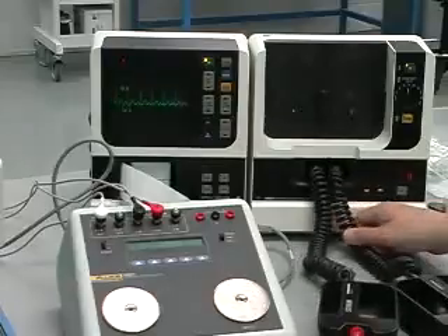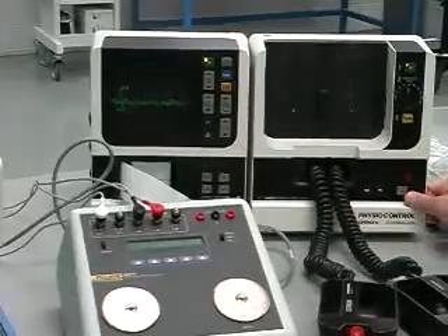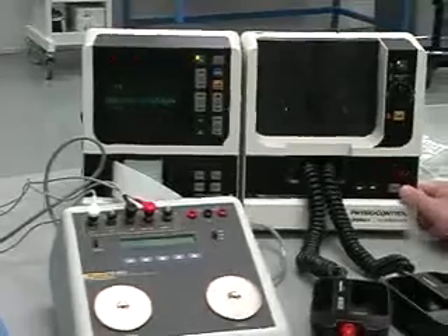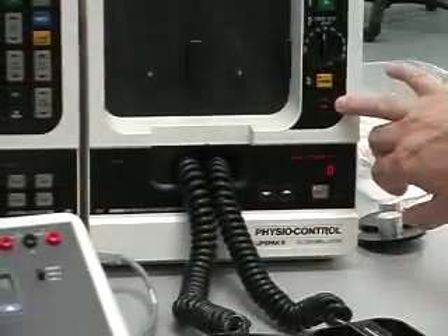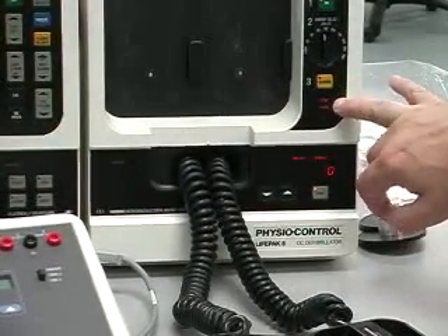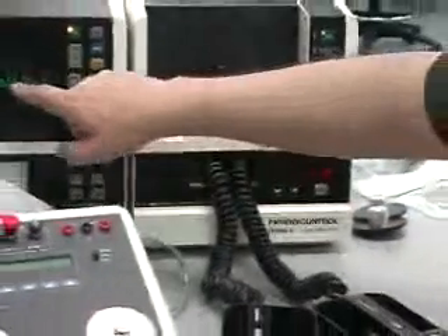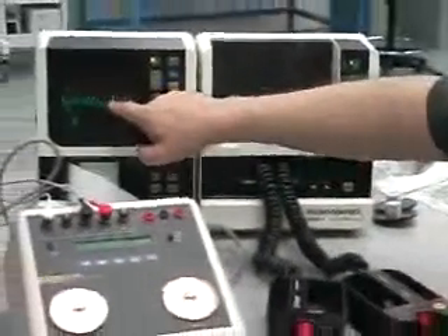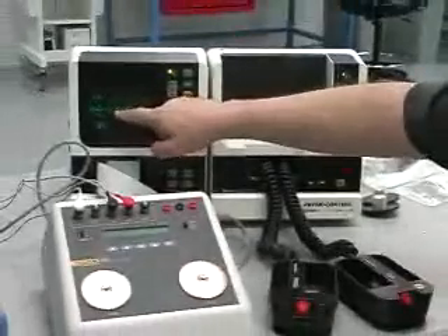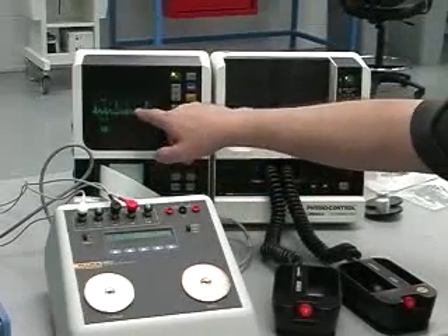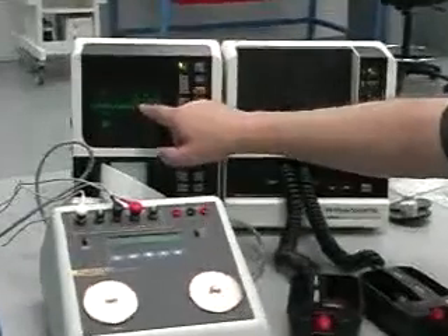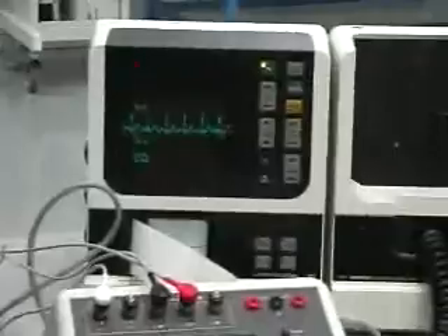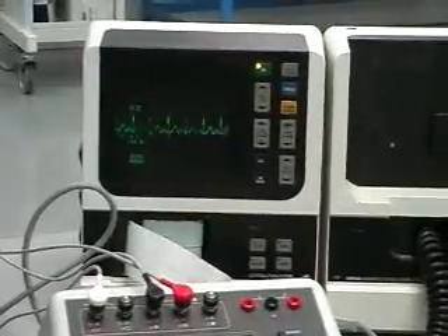So with this, on the defibrillator, you do have a synchronization control or a push button. And once you push that, first off, you get an indication on the defib that it is in a synchronization mode, and you also get a high intensity blip on the ECG waveform. So you can see sometimes it is riding at different spots on the ECG. It just depends when it does sense the wave.